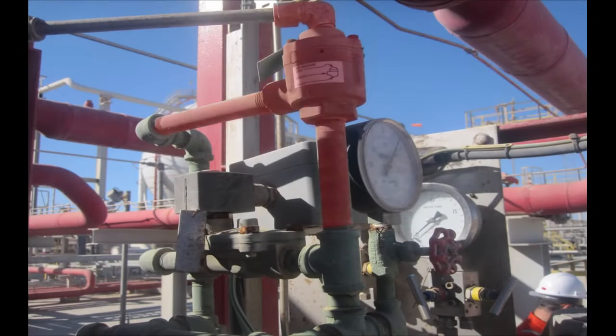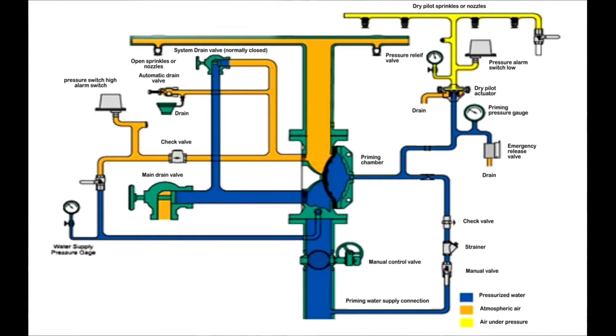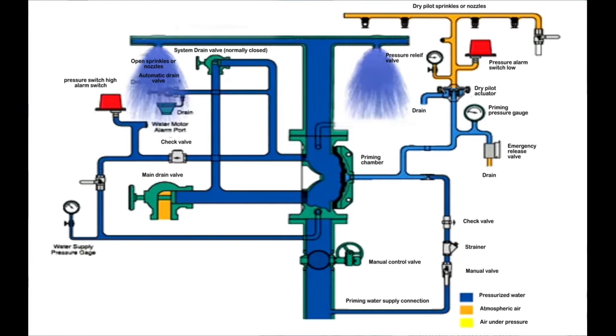Another method of activating the deluge system is the dry pilot actuator. The yellow color represents pressurized air between the dry pilot actuator and the sensing element, the blue color represents pressurized water, and the orange color represents atmospheric air. The dry pilot actuator is connected to the priming loop from one side and to the drain open to the atmosphere from the other side. In case a sensing element detects high temperature, the pressure on top of the dry pilot actuator is released, opening the path to the drain, and therefore releasing the priming pressure to open the deluge system.